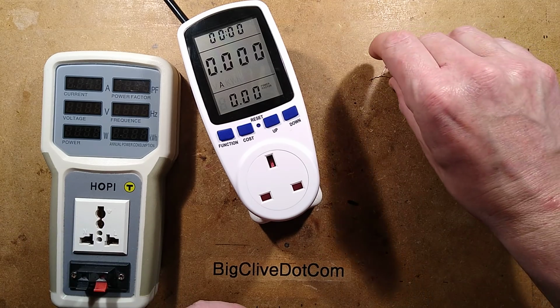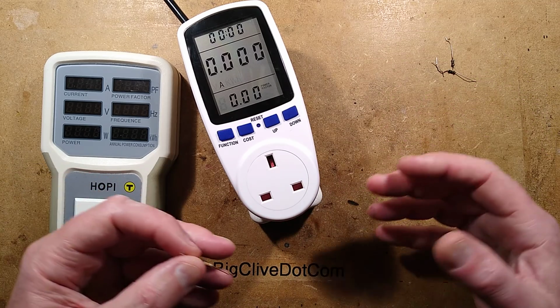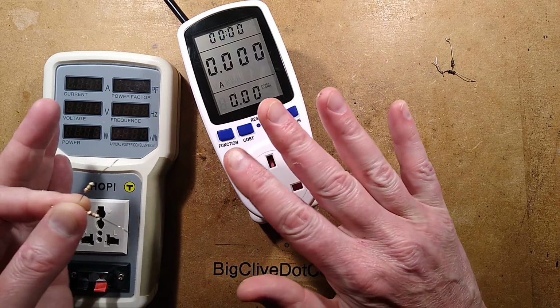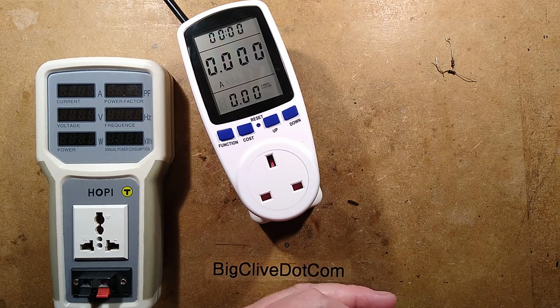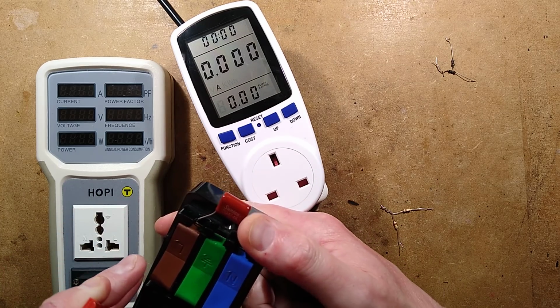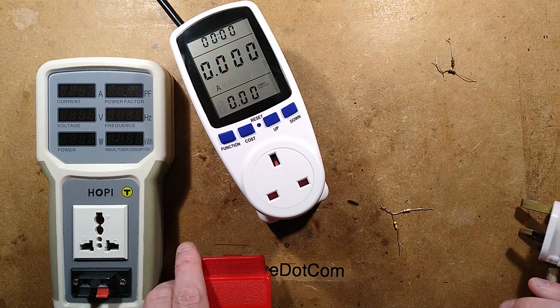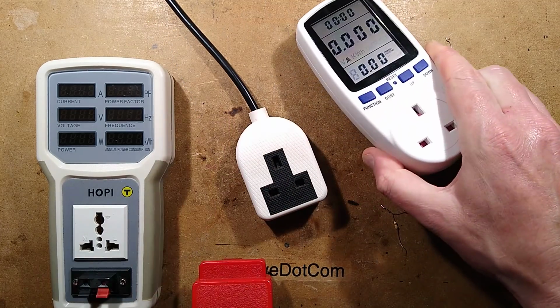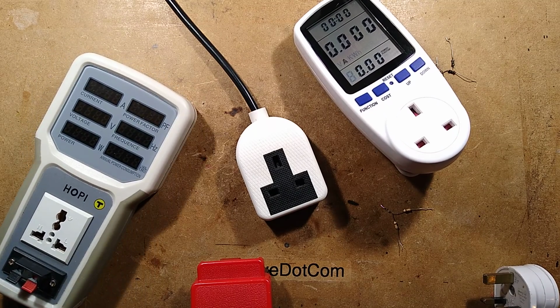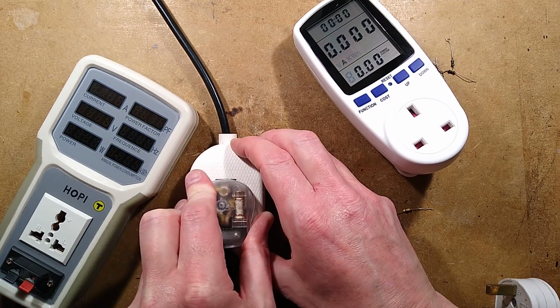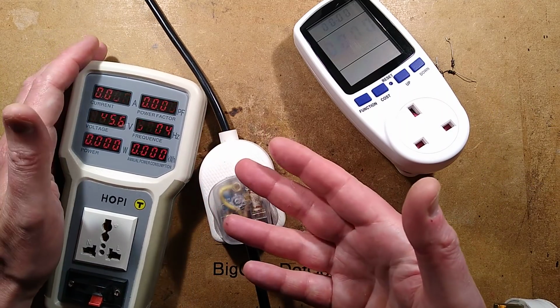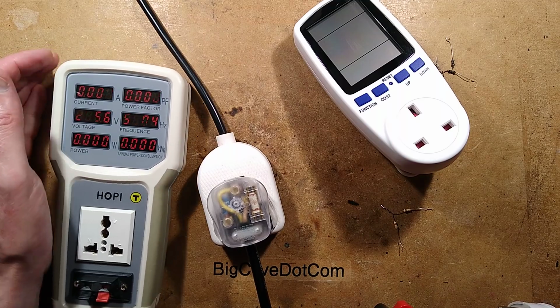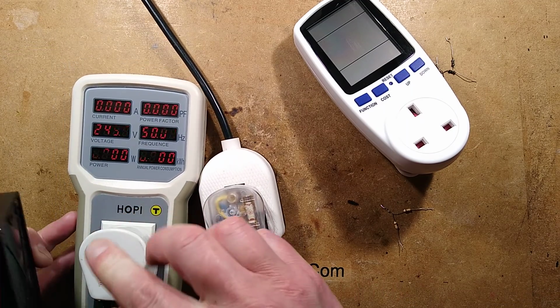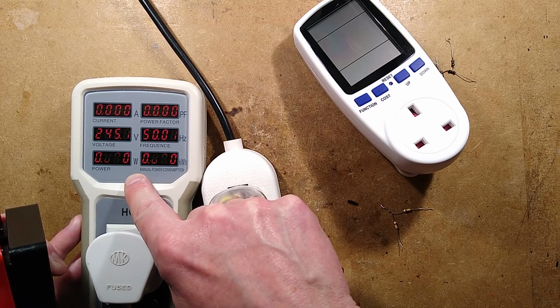Right, anyway. Once I'd restored normal vision and reset the breaker, I stuck these in, and it wouldn't read them, it was too low, but the Hopi wouldn't read it either. But there is an interesting thing. If I bring up my quick test, I've actually got just a capacitor stuffed in it, because one of the things that's slightly annoying about the Hopi is that it doesn't show a very poor power factor load. So for instance, some of the LED lamps that are rated 1/2 watt just won't show up in the Hopi, and I'll show you that. So I'll plug this in, and this is actually passing current, but because the power factor is so bad the Hopi just ignores it completely.